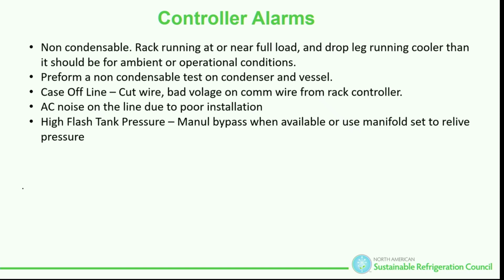But just simply, why do we get non-condensables? People ask me that all the time. Because we have a bad practice of not purging our hoses. We're charging that charging line, and we're not purging it with vapor before we put liquid in. We're not only creating dry ice, but we're putting non-condensables in. And CO2 seems to be a little bit more susceptible. It happens more often.